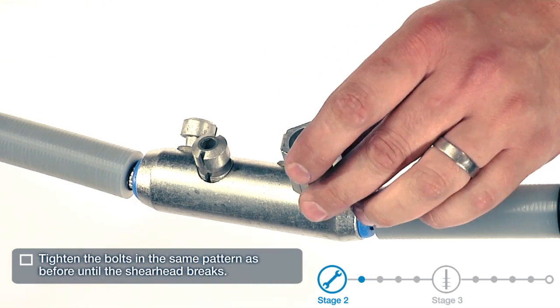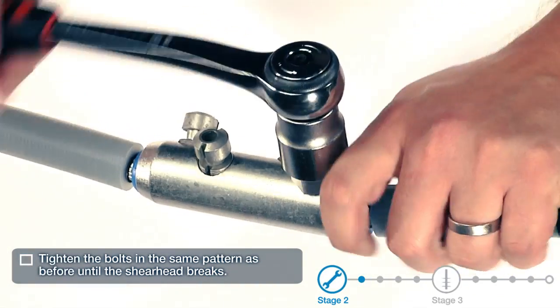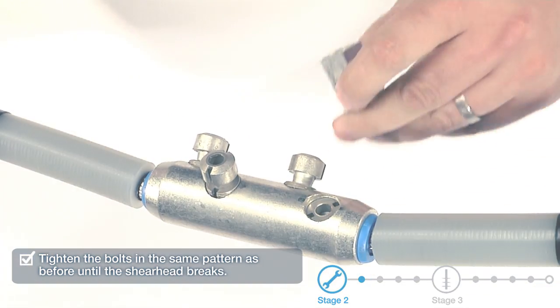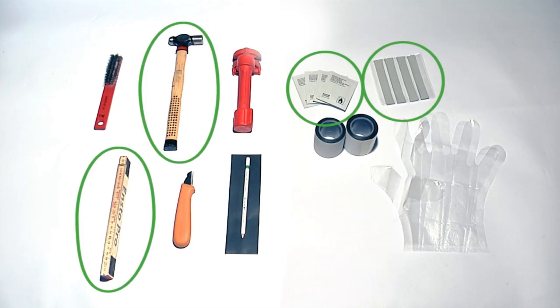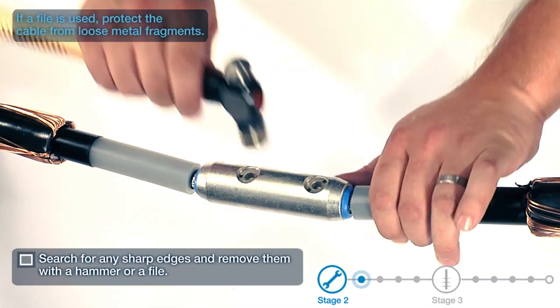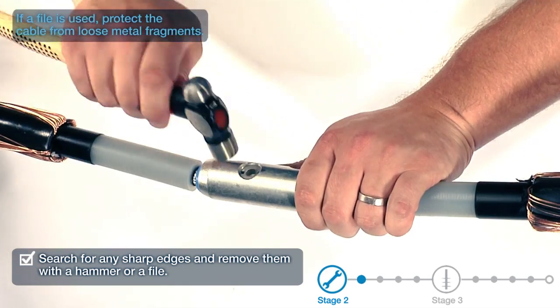Tighten the bolts in the same pattern as before until the shear head breaks. Search for any sharp edges and remove them with a hammer or a file. If a file is used, protect the cable from loose metal fragments.